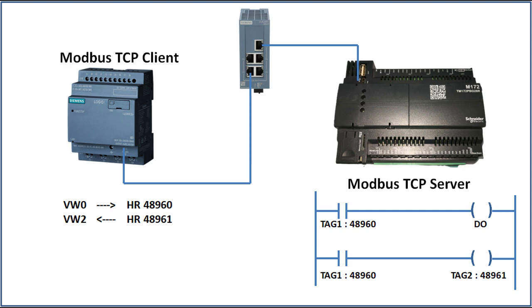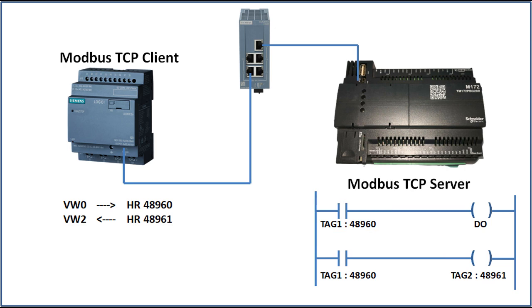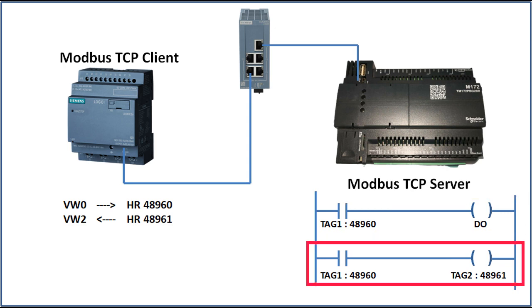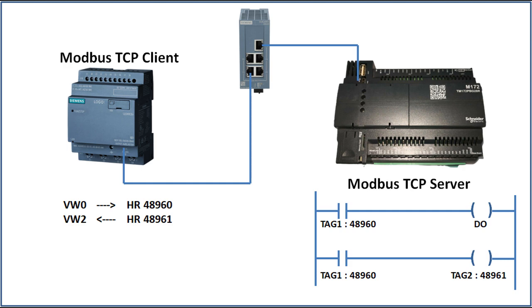I have set up a Schneider M172 PLC as a Modbus server and configured two holding registers at addresses 48960 and 48961. At address 48960, I have configured a digital output of the M172 PLC, and at address 48961, we will read the feedback of that digital output. I will trigger one address from Logo PLC to turn the DO on and off, and I will demonstrate two different methods of configuration in this video.